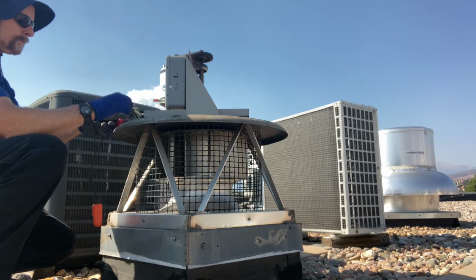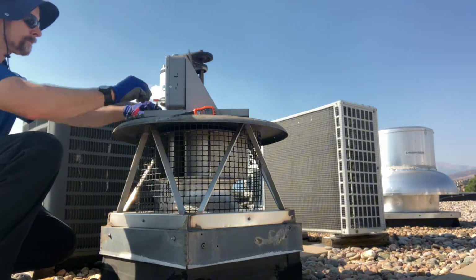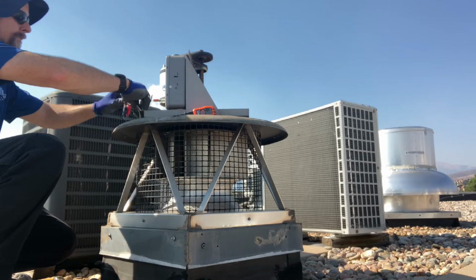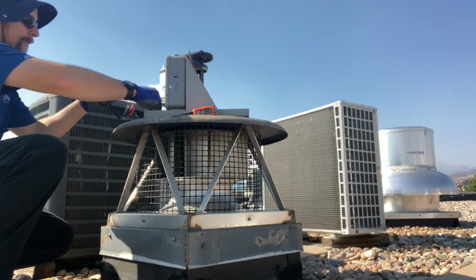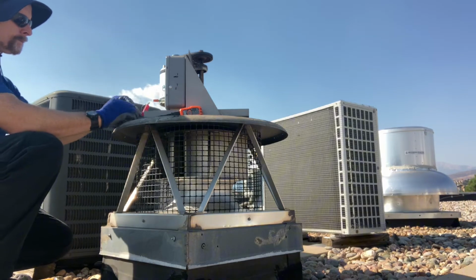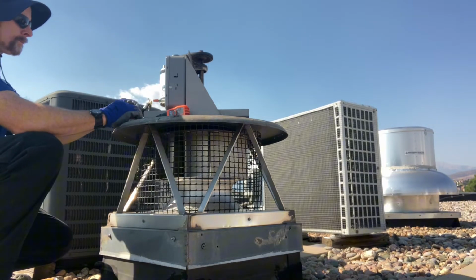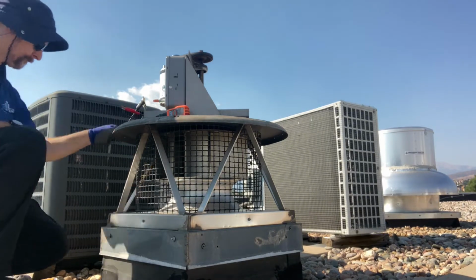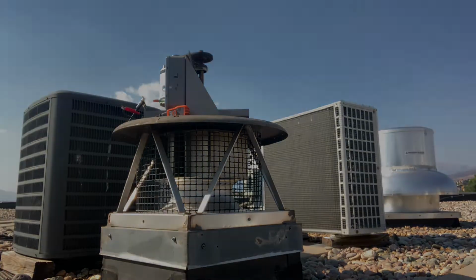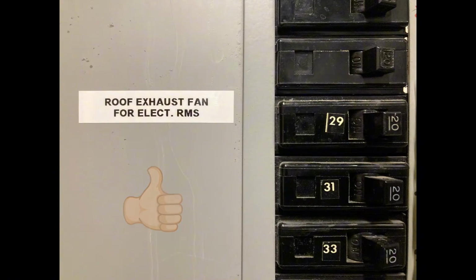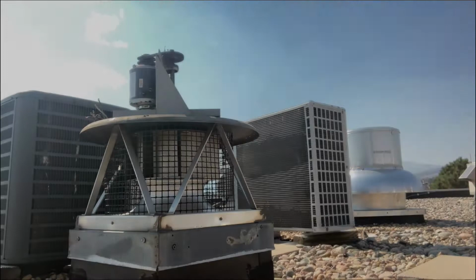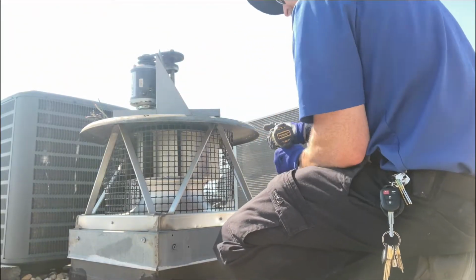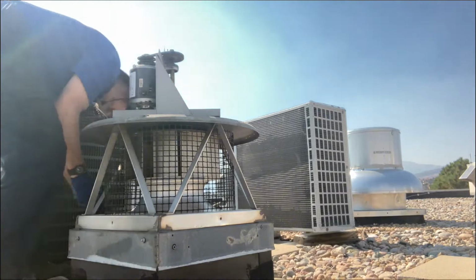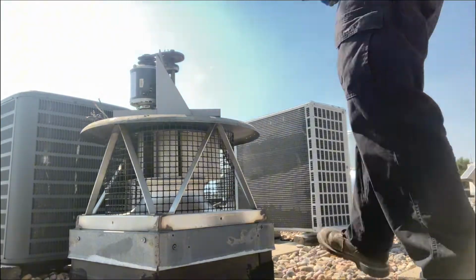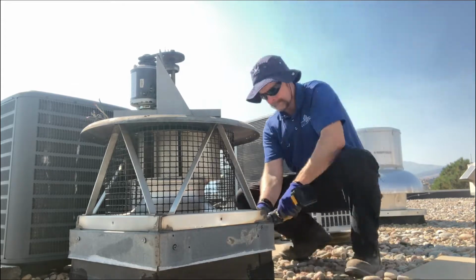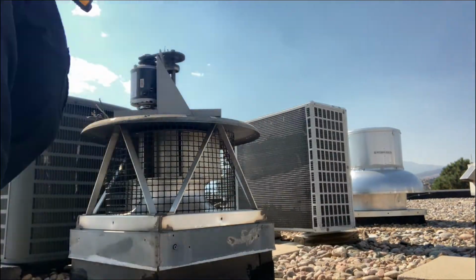And then what I'll do is I'll go down with the receiver and slowly scan the circuit breaker panels until I find the circuit breaker that controls this unit. If that doesn't work, then I'll have to figure out an alternative method. And then I'll label the breaker like so. So now we know what circuit breaker controls that exhaust fan. So now with the power safely off, we'll unscrew it from the roof curb, lift the unit off, and prepare the roof curb for the new unit.